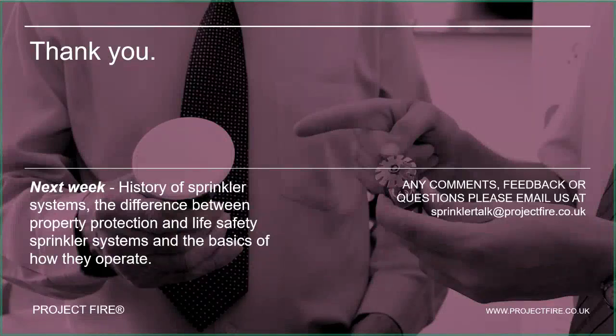Question: do we use copper pipework? No, we generally don't, though I believe copper does appear in the standards as an acceptable material. In commercial sprinklers we use plain steel pipe, and we can also use galvanized pipe or CPVC plastic pipe. A plastic-based pipe is typical for residential and domestic systems, but you can equally use steel pipe for residential and domestic as well. There are options there, but copper is quite rare, as you rightly say, because of the cost of that material.